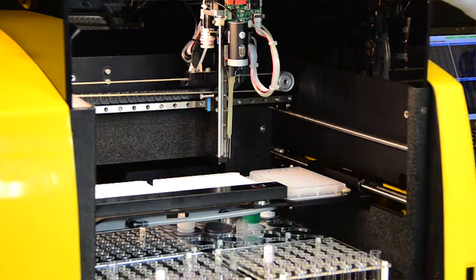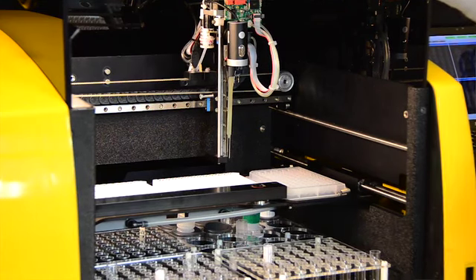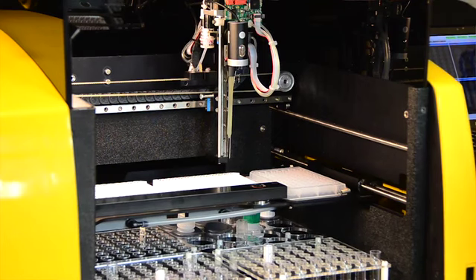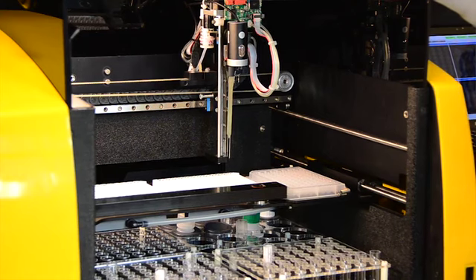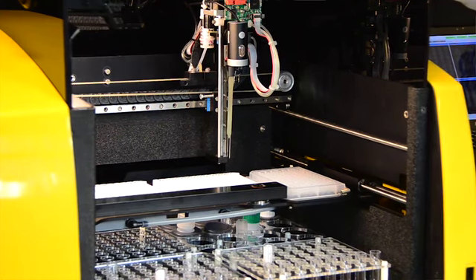The reason we do this is because peristaltic pumps are inherently variable. They change over time, they change with temperature. We do use them on our instrument, but we use them for the wash pump only and for the waste pump. So they will be helping to deliver wash to the wells because that volume is not as critical. Then let's say a 20 microliter sample dispense into the well. That's a critical volume and it must be accurate.